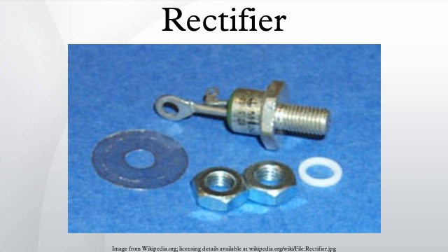A 12-pulse bridge consists of two 6-pulse bridge circuits connected in series, with their AC connections fed from a supply transformer that produces a 30-degree phase shift between the two bridges. This cancels many of the characteristic harmonics the 6-pulse bridges produce. The 30-degree phase shift is usually achieved by using a transformer with two sets of secondary windings, one in star connection and one in delta connection.